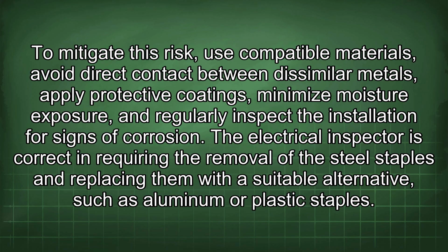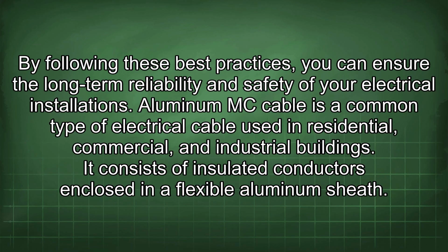The electrical inspector is correct in requiring the removal of the steel staples and replacing them with a suitable alternative, such as aluminum or plastic staples. By following these best practices, you can ensure the long-term reliability and safety of your electrical installations.